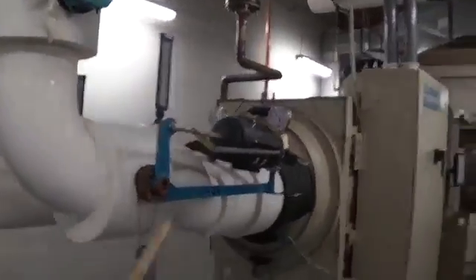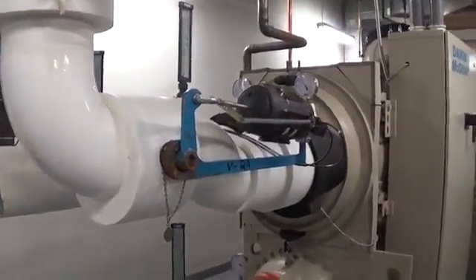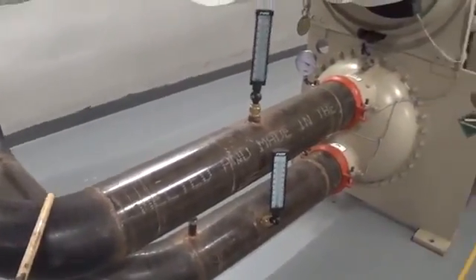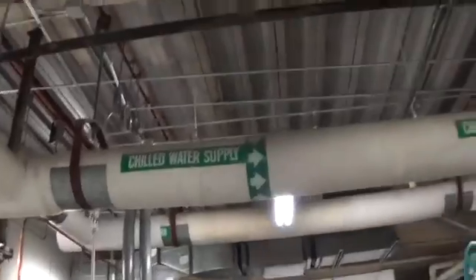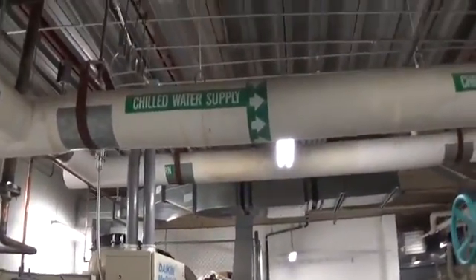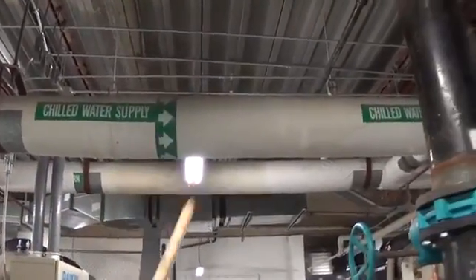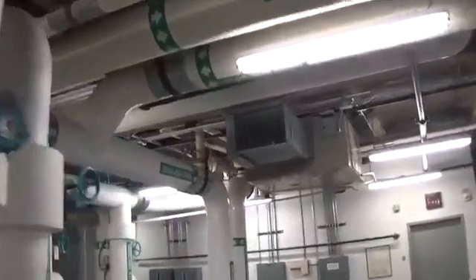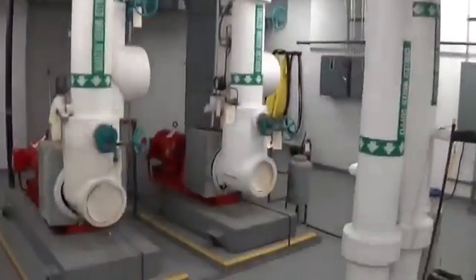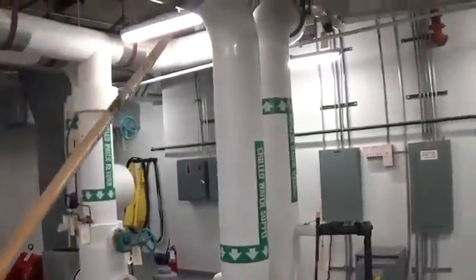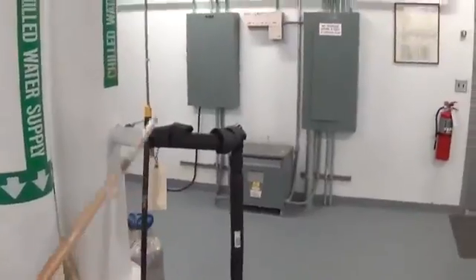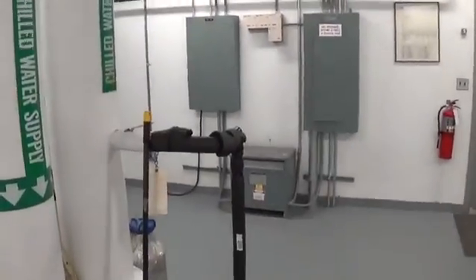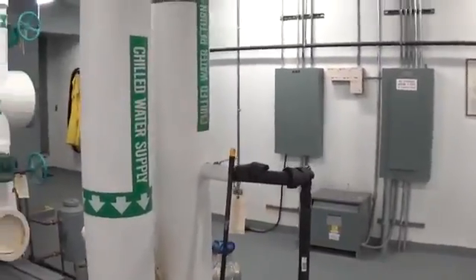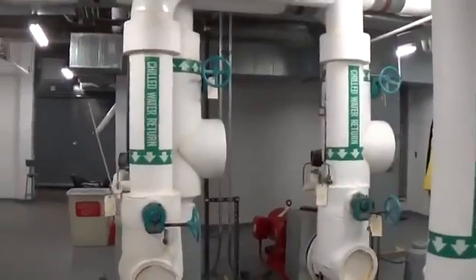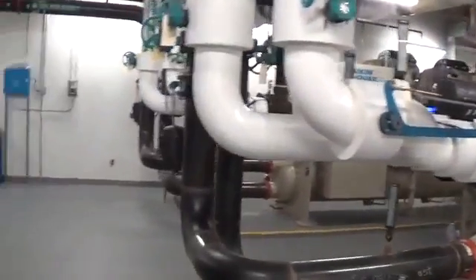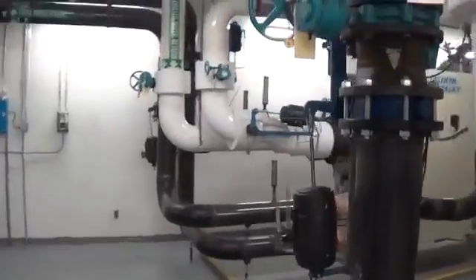So we have two sides of the chiller. We have the chill water side, which has the insulation on it, and we have the condensing side, which is non-insulated because it's warm. And pretty much what we do is we make cold water with the compressors and the refrigerant. You can see the chill water pipes. We'll follow them. And they come across the top of the chiller plant, and they go to a series of pumps. These pumps pump the chill water up and down through the building to a series of air handler coils staged throughout the facility, and that has a fan behind it which blows the cool air into distribution boxes in the office space. And that's an oversimplification, but that's pretty much how it works.